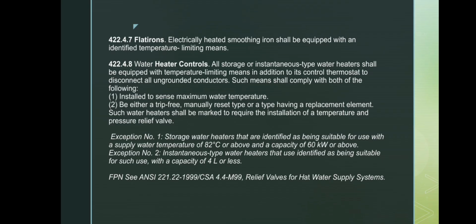There are two exemptions: large storage heaters designed for 82 degrees Celsius or higher and 60 kilowatts or above, and very small instantaneous heaters, 4 liters or less, specifically identified for such use. For reference, see the ANSI CSA standard for relief valves.